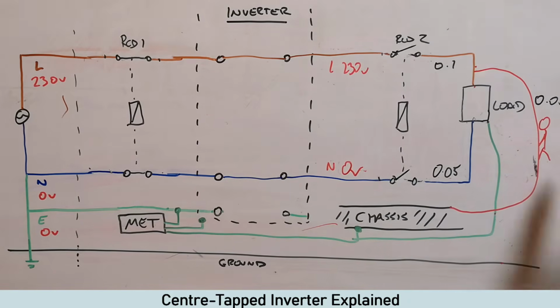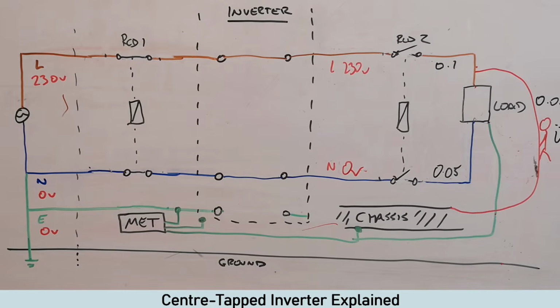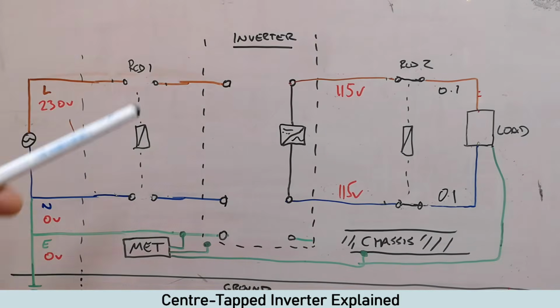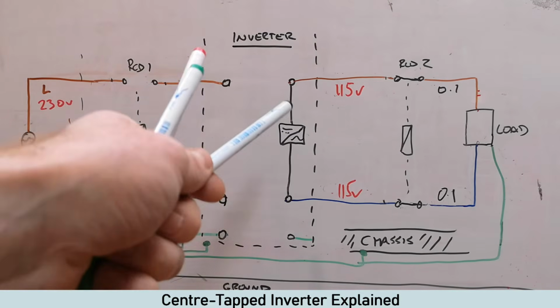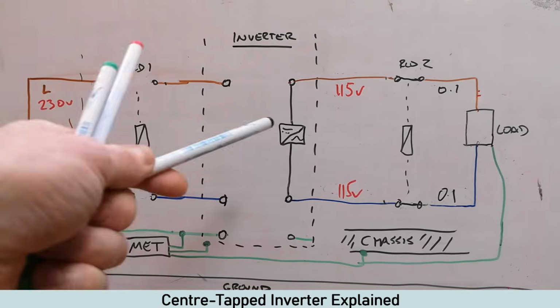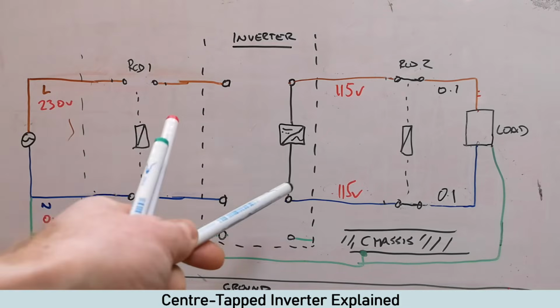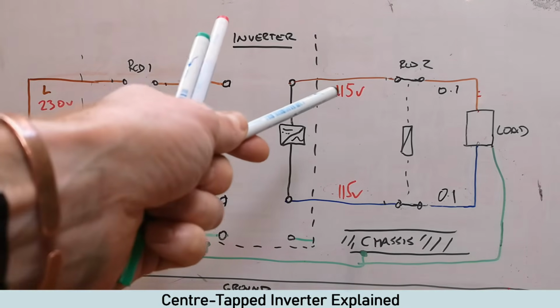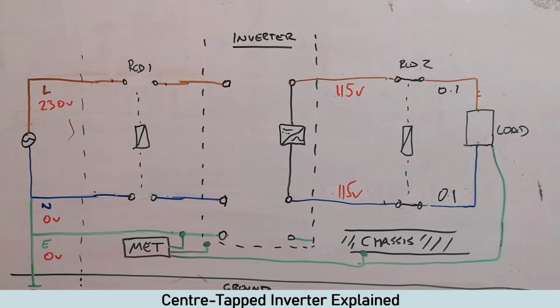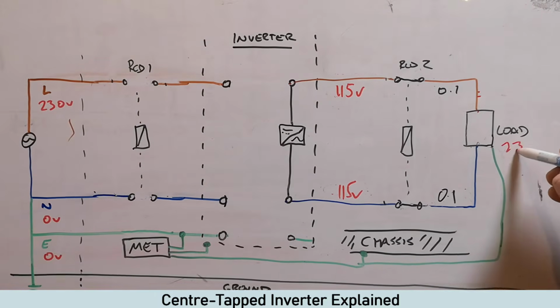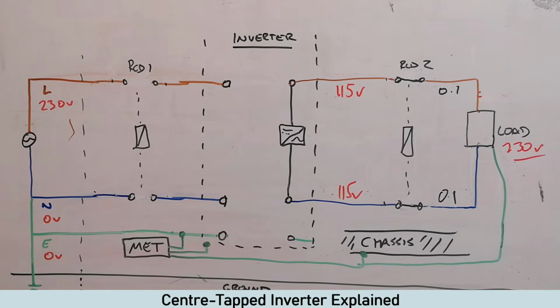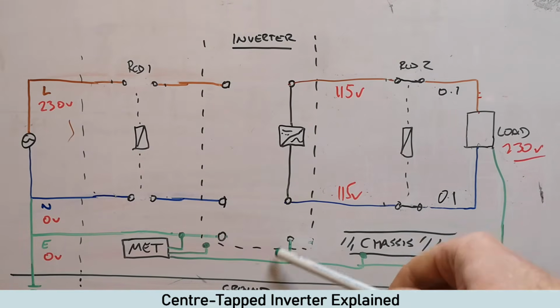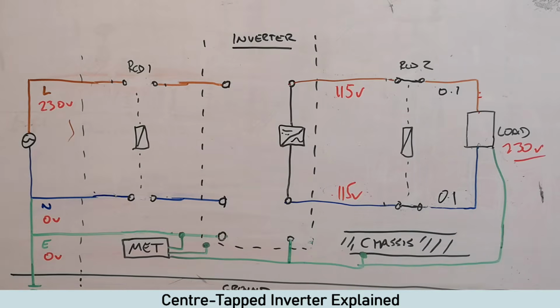Happy days. So then you're very happy that it's been isolated. So what happens when the inverter's on? The situation now is the inverter is on inverter, so there's no power coming in. Obviously this bypass link has gone. The inverter's on, so we're getting 115 volts and 115 volts to the load. So what does that mean for the load? Well, the load's on, it's happy, 230 volts. Sorry, I've just included that earth there because that was missing before.